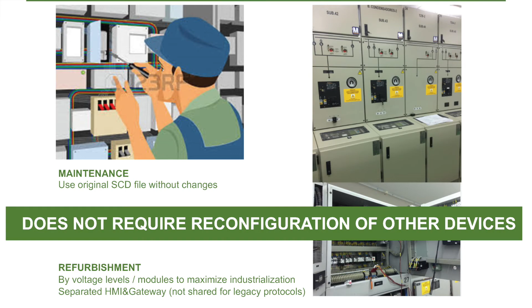So imagine the case of a new substation. Once the central systems have automatically assigned the IP addresses, chosen the IDs, and given the ID names, they put all that information in the file CNF, then it shall send a command line to the substation configuration tool with an argument to create the new SCD file and a link for it to download that input file CNF from a shared database. Then it shall validate that file, download the referenced ICD templates, and start to build the SCD file.